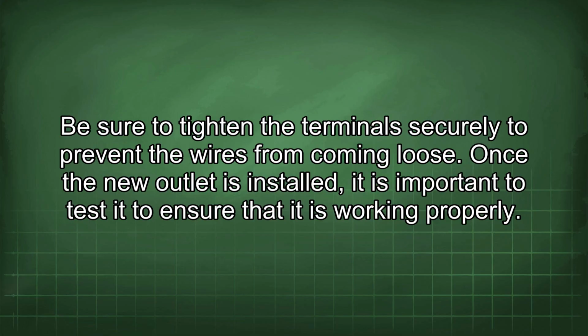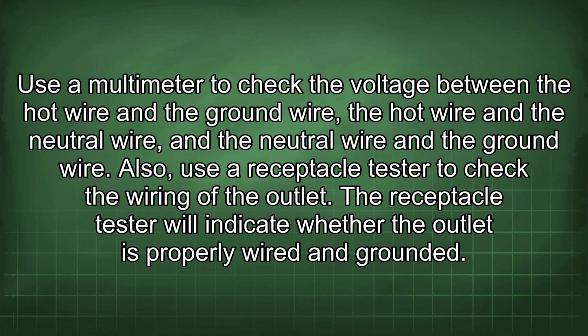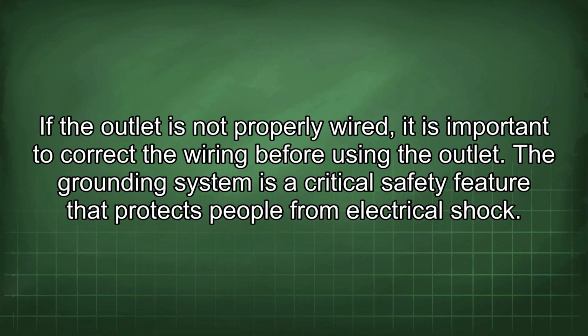Once the new outlet is installed, it is important to test it to ensure that it is working properly. Use a multimeter to check the voltage between the hot wire and the ground wire, the hot wire and the neutral wire, and the neutral wire and the ground wire. Also, use a receptacle tester to check the wiring of the outlet. The receptacle tester will indicate whether the outlet is properly wired and grounded. If the outlet is not properly wired, it is important to correct the wiring before using the outlet.